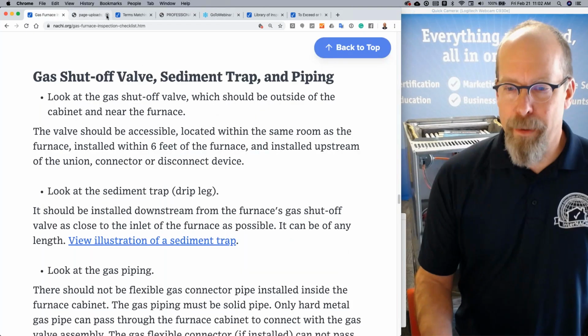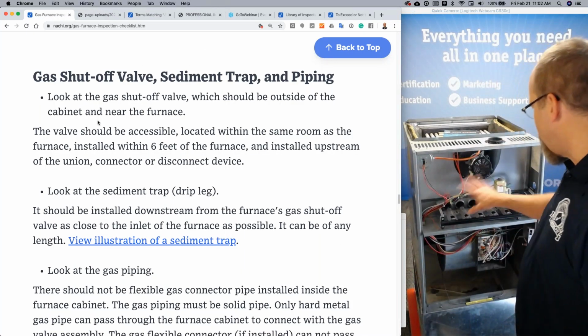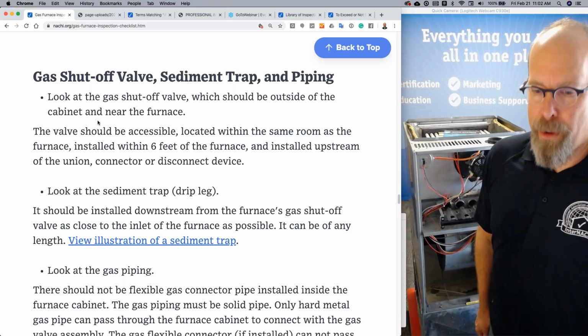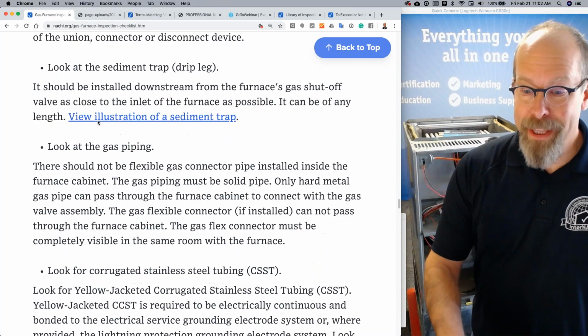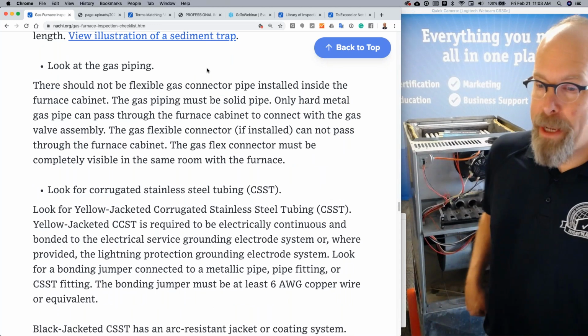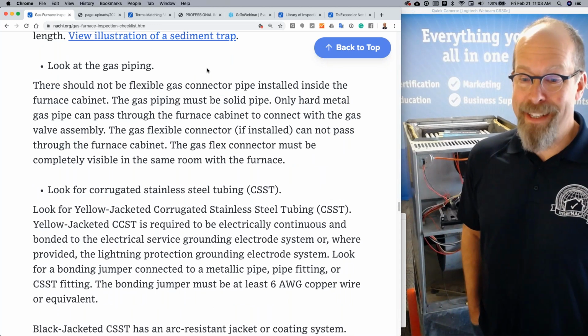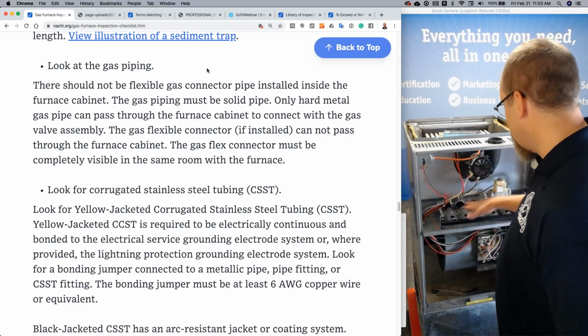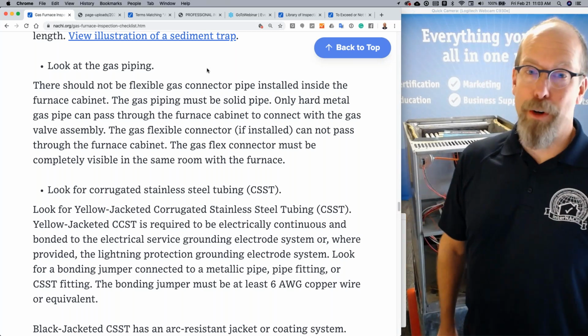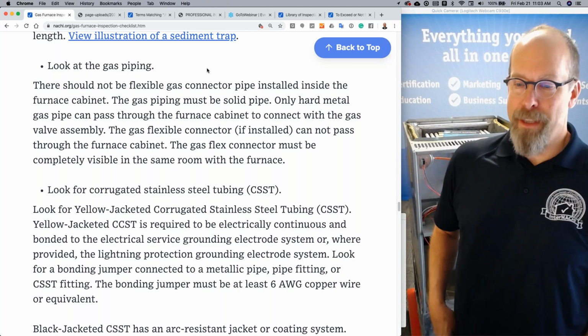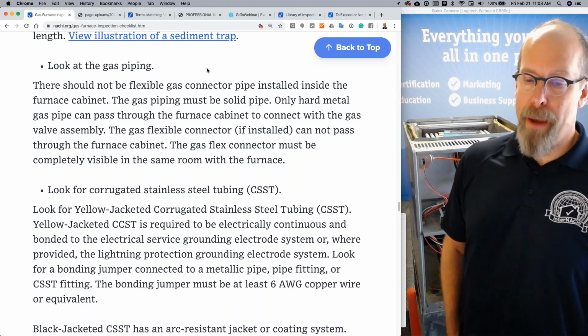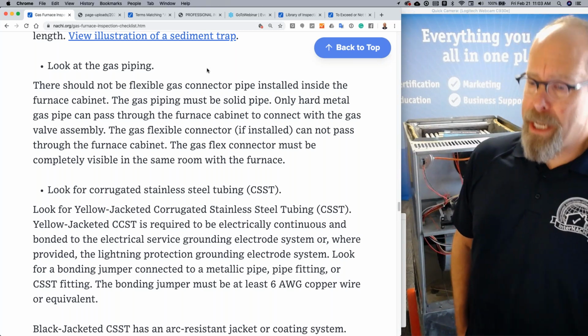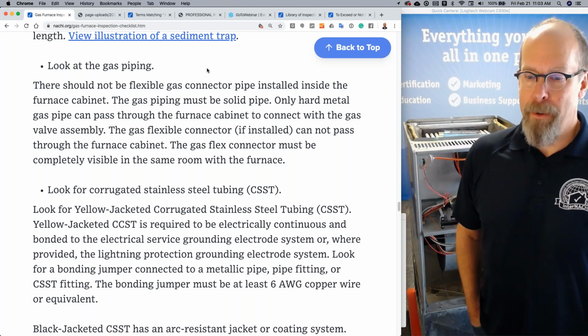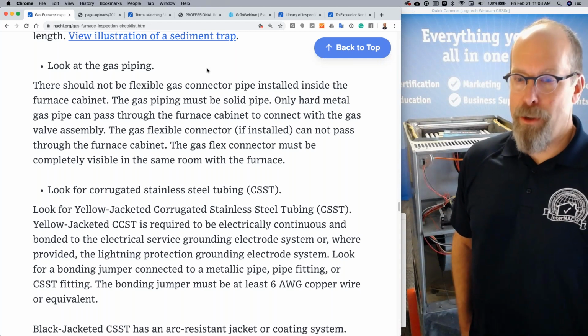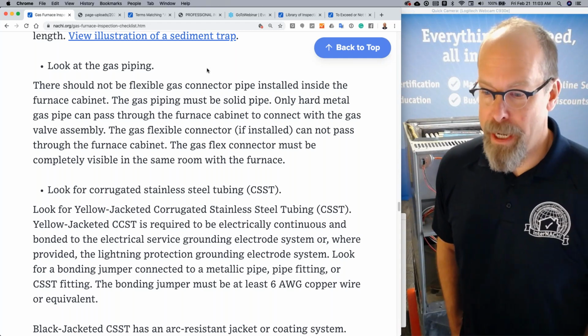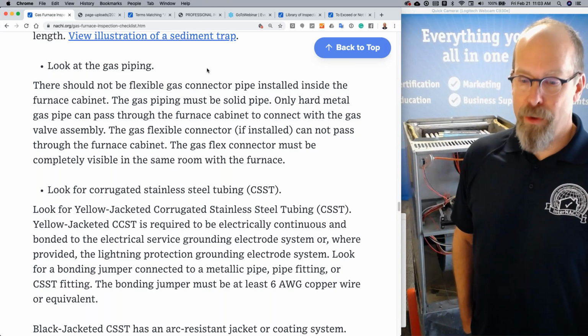Sorry if you're listening to the podcast of this, but we've got a furnace here and I'm just pointing at the actual components themselves. Look at the gas piping. There shouldn't be any flexible gas connector pipe installed inside the furnace cabinet. If you see a flexible gas pipe installed in the furnace cabinet, which you will at the House of Horrors, that's a defect. The gas piping should be solid pipe. Only a hard metal pipe can pass through the furnace cabinet to connect with the gas valve assembly. There may be exceptions, but that's up to the local code. The gas flexible connector, if installed, cannot pass through the furnace cabinet.